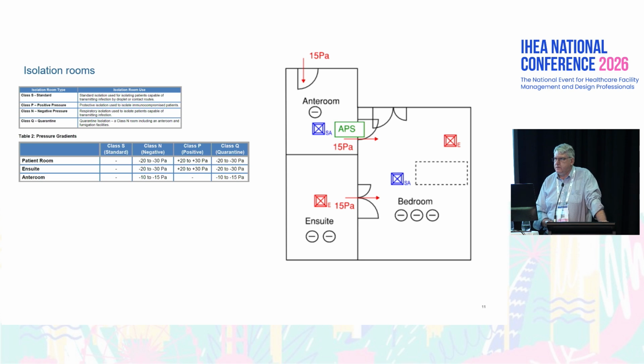At the moment in Metro North, I don't believe—unless Caboolture has—we don't have anything that runs with the dual pressure differential. Everything was designed back in the late 90s, so we've only got a 15 pascal step through our areas currently, and trying to retrofit those areas is next to impossible, as you'd all know. But there's some really good guidance there when thinking about negative pressure in isolation rooms.